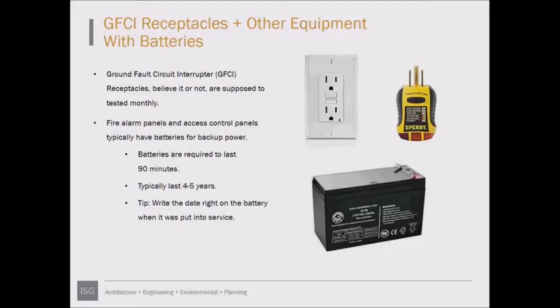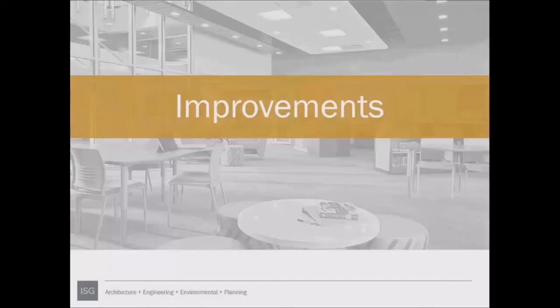The black battery shown at the bottom is found in all fire alarm and access control panels, used for backup power. The battery is also supposed to hold 90 minutes of backup, so this is a great opportunity to test them and make sure they last. Typically they're good for 4 to 5 years, and we recommend writing the date directly on the battery when you put it into service.